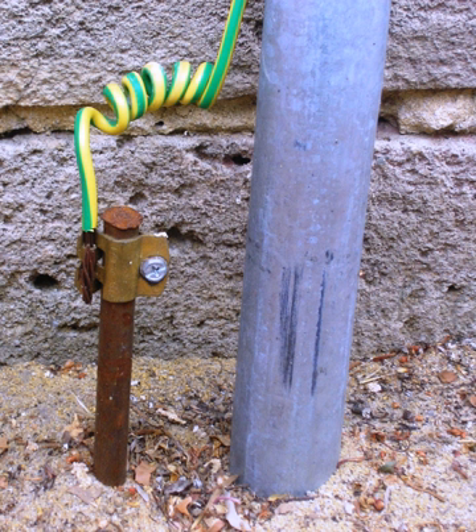For an isolated device, touching a single powered conductor does not cause a severe shock, because there is no path back to the other conductor through the ground. However, shocks and electrocution may still occur if both poles of the transformer are contacted by bare skin. Previously, it was suggested that repairmen work with one hand behind their back to avoid touching two parts of the device under test at the same time, thereby preventing a circuit from crossing through the chest and interrupting cardiac rhythms, causing cardiac arrest.